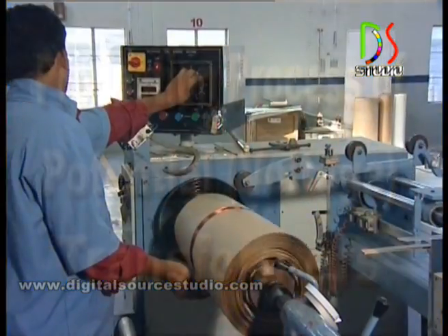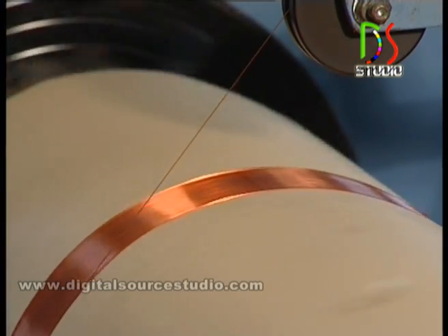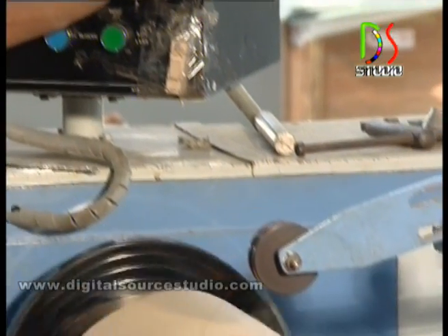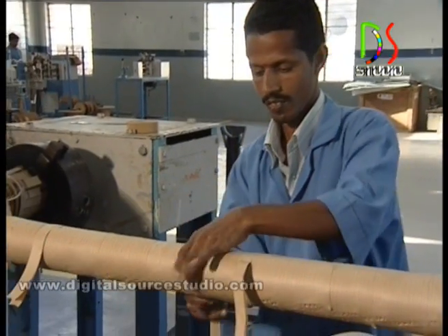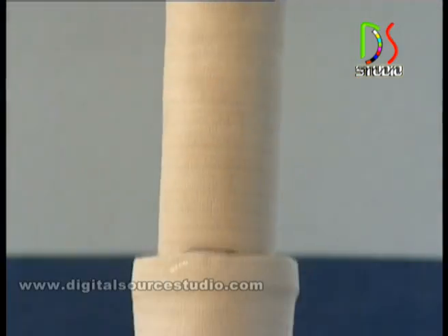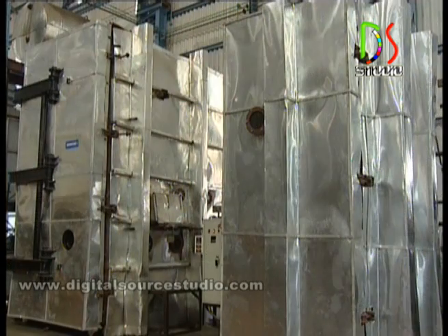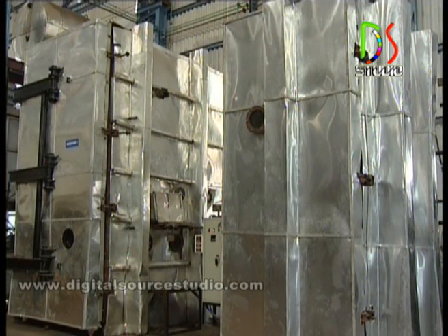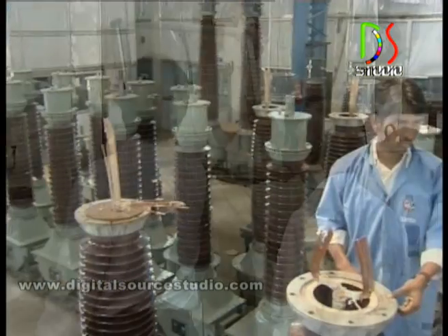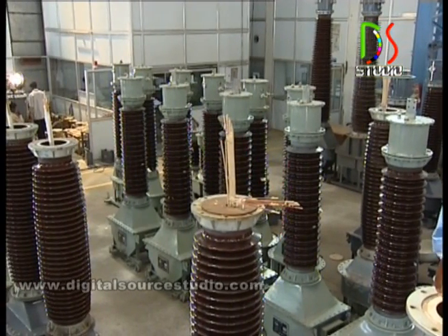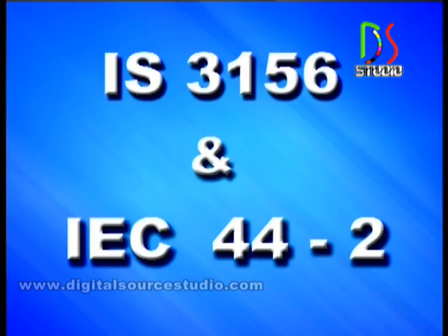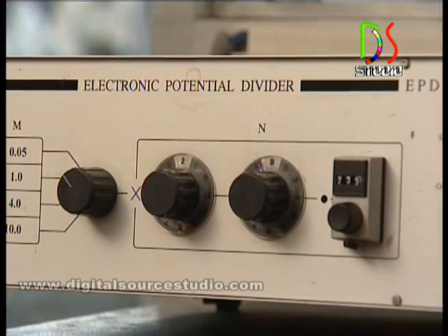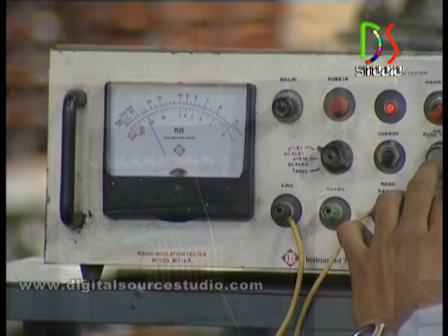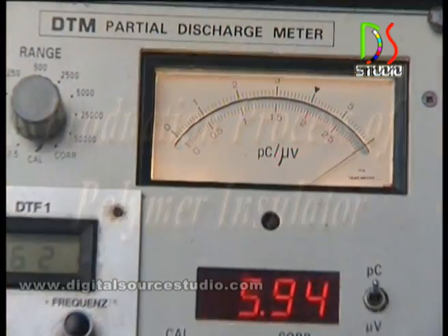Production process of potential voltage transformers. The primary winding and HT insulation is done simultaneously on a special coil winding machine as per the specification. Secondary coil is wound separately and inserted inside the insulated primary coil. The entire coil is fitted into lamination assembly. The whole assembly is loaded into a vacuum impregnation plant and then filled with transformer oil after the specified time, temperature, and vacuum are attained. Final assembly of the voltage transformer is completed and subjected to tests as per IEC standards: accuracy test, induced overvoltage test, 3 kV test on primary and secondary, partial discharge test.